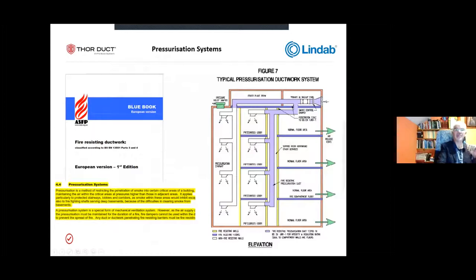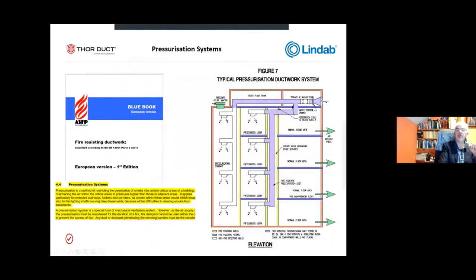Pressurisation systems are another area to be aware of. Multi-compartment pressurisation ducts provide positive pressure into protected escape routes so that when a door opens, smoke does not migrate in. These ducts must also be insulated — you do not want a fire in one compartment causing the duct to heat up so that you're pumping air in excess of 100°C into an escape route. Insulation and temperature control are therefore prevalent across all these system types.